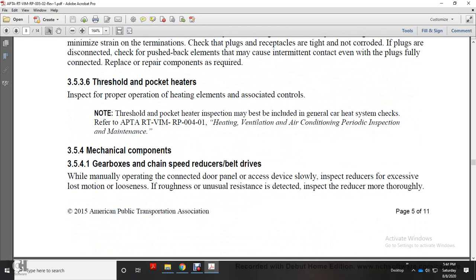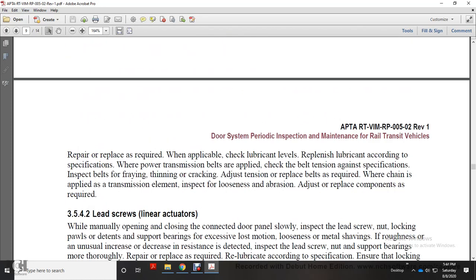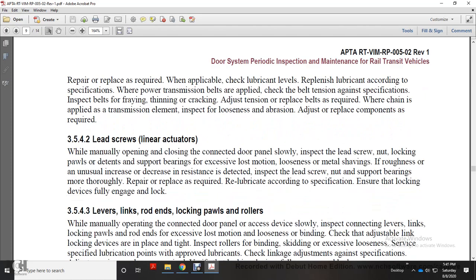Alright, 354, mechanical, gearbox, chain, speed reducer, belt drive. With the manual operating device of the door panel accessible, slowly operate and inspect the reducer for excessive loss of motion, roughness, and unusual resistance. Detect and inspect the reducer more thoroughly. Repair or replace as required when applicable. Check the lubricant level and replenish lubricating oil according to specification. When a power transmission belt is applied, check the belt tension again for the specification. Inspect belts for fraying and cracking, adjusting tension of the belts as required where chain is applied. As transmission elements, inspect for loosening and abrasion, adjusting and replacing the components as required.